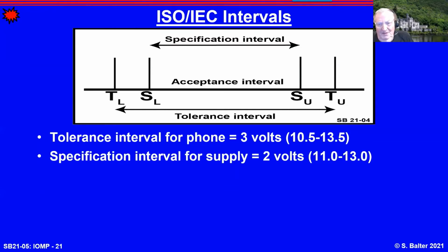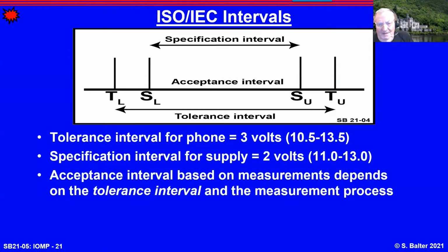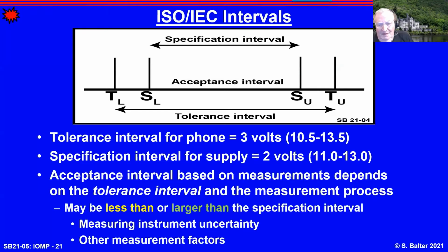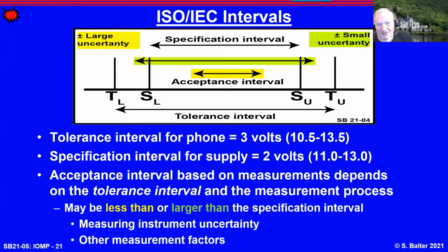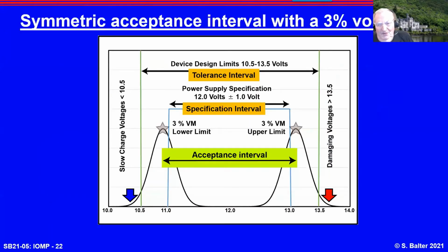We're now going to decide whether to accept it. The acceptance interval will depend on the tolerance and the measurement process. If I have a high uncertainty in the measurement, I will have a very small acceptance interval. Here, if I have a large, good instrument with small uncertainty in the process, I can have a much larger acceptance interval.